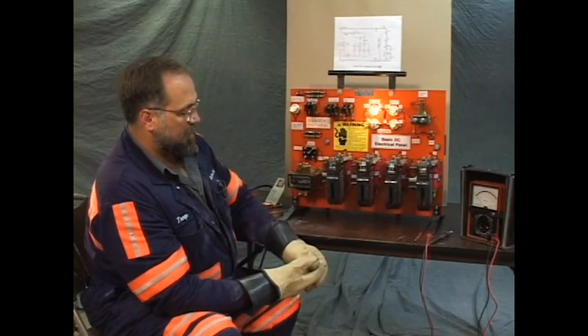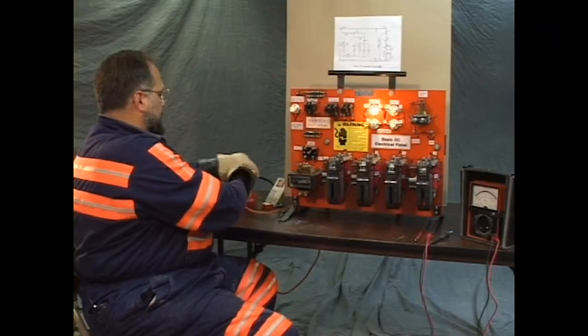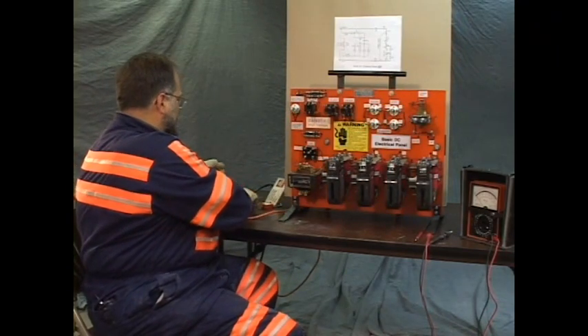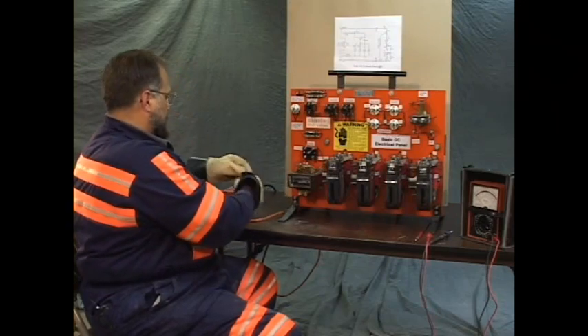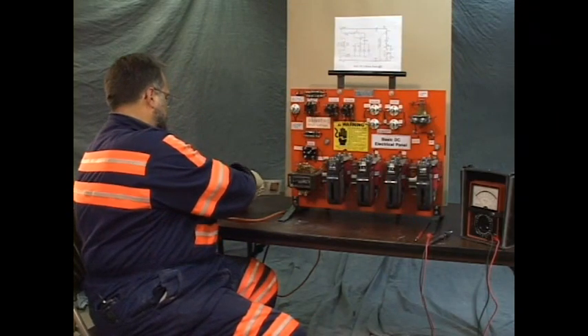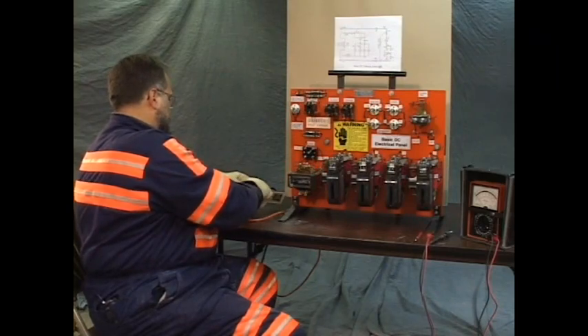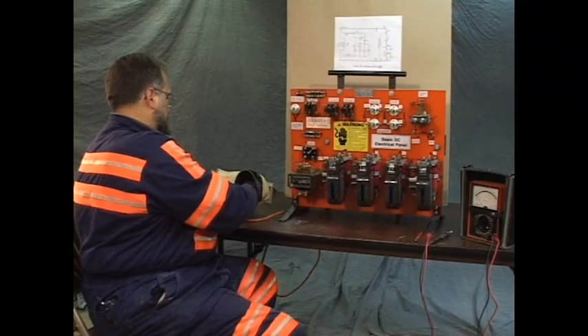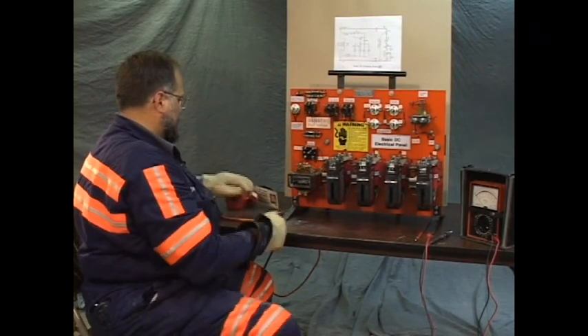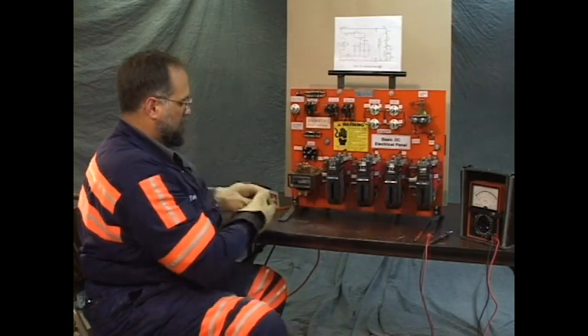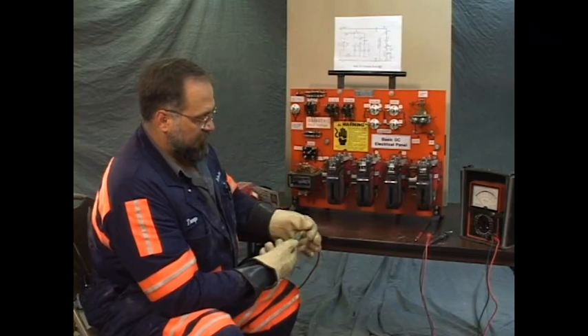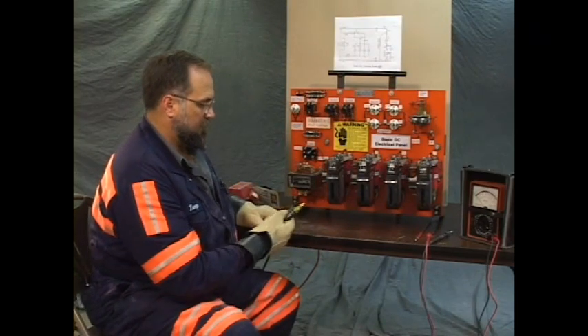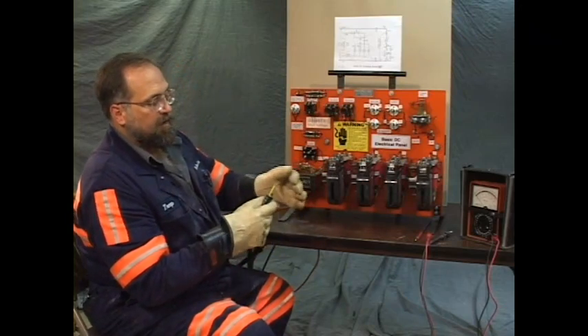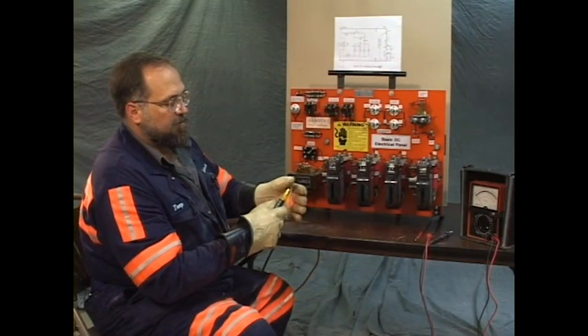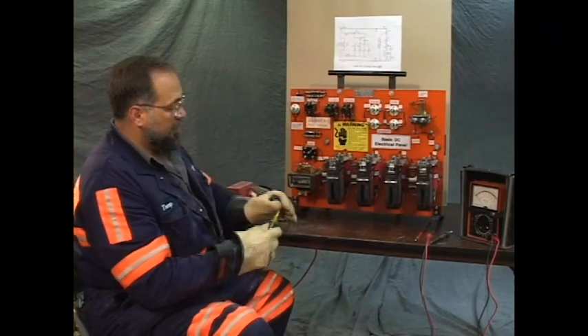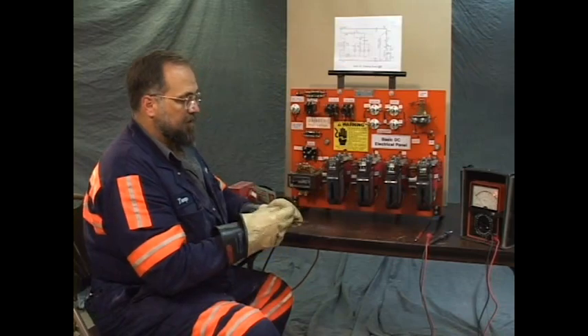Let's take the power off, lock and tag, make this panel safe, and then we'll look for the problem. We use this voltage detector. It does a little nuisance flash at times. If you make a sudden movement with it, it'll flash. But should it actually detect power, it'll be a constant light and a constant tone.